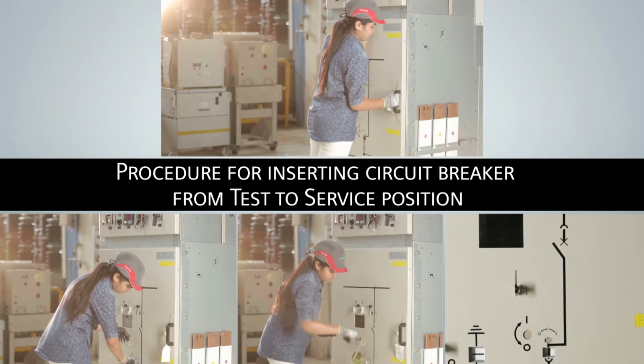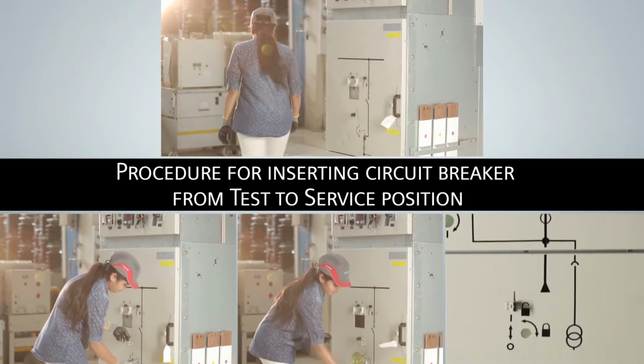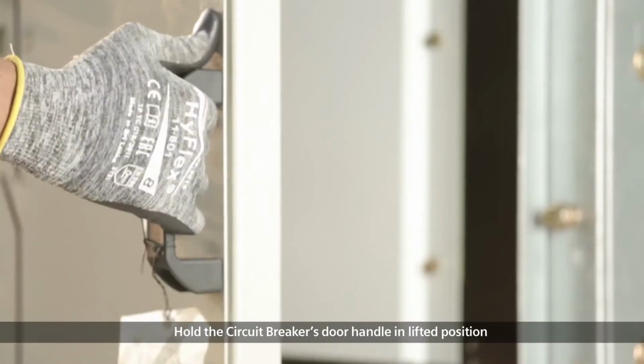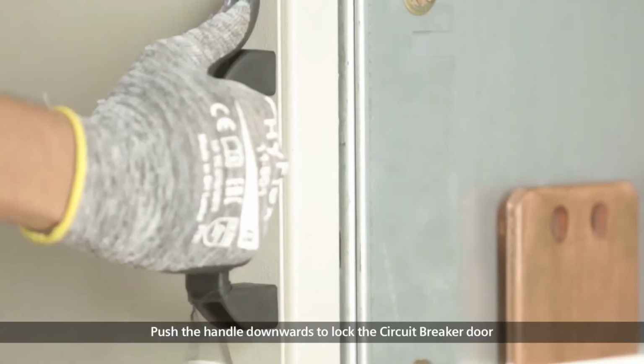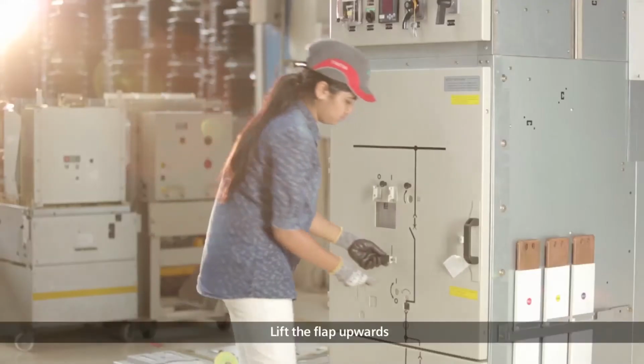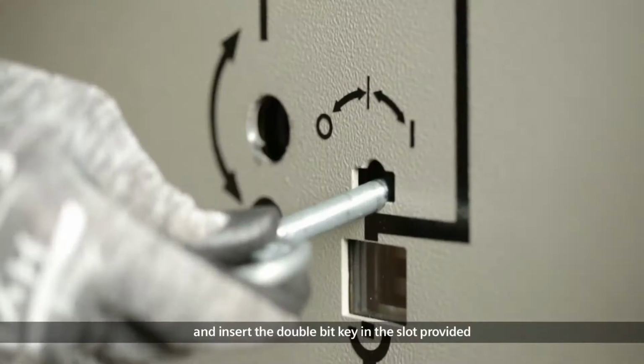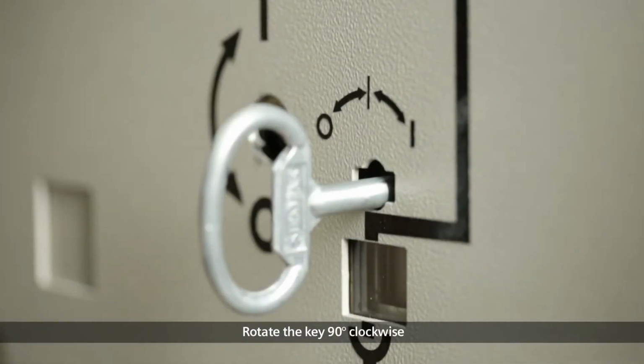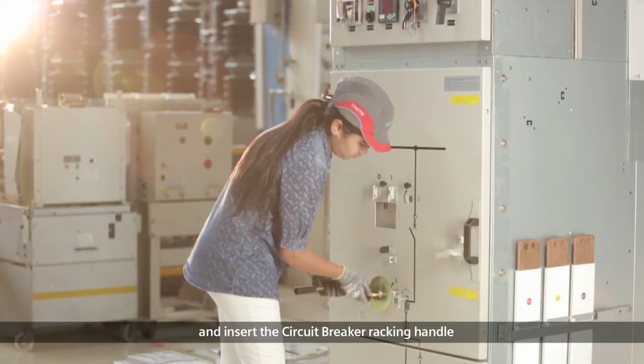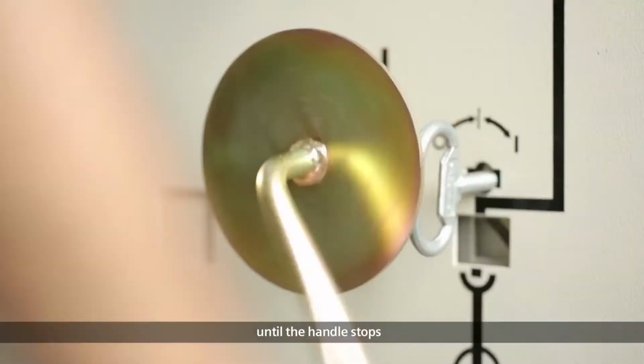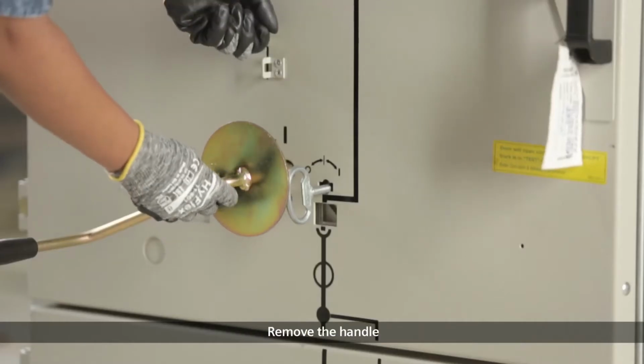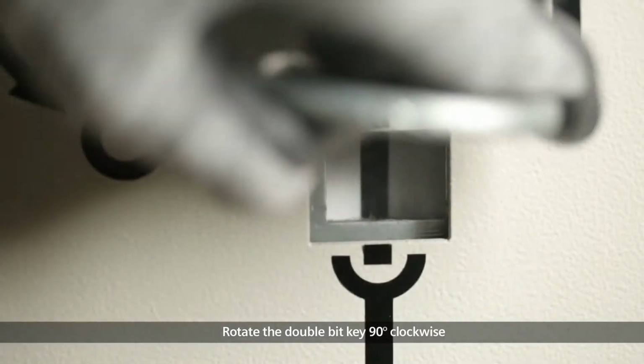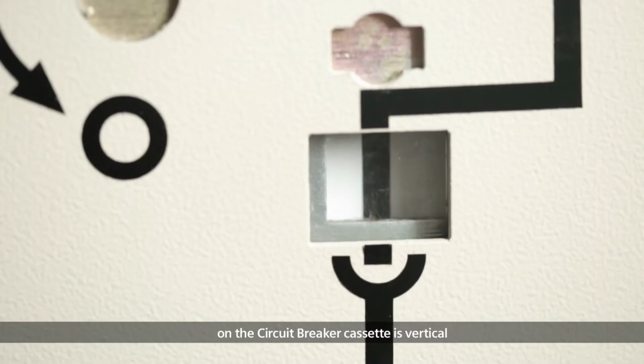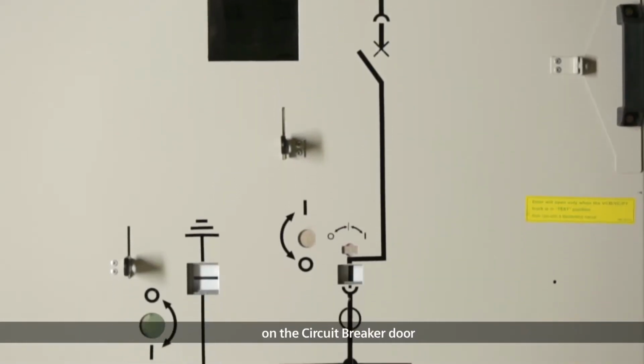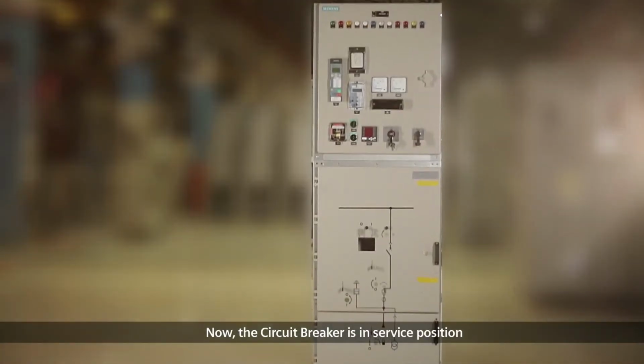Procedure for inserting circuit breaker from test to service position. Hold the circuit breaker's door handle in lifted position and close the door. Push the handle downwards to lock the circuit breaker door. Lift the flap upwards and insert the double bit key in the slot provided. Rotate the key 90 degrees clockwise and insert the circuit breaker racking handle. Rotate the handle clockwise until the handle stops after approximately 18 rotations. Remove the handle. Rotate the double bit key 90 degrees clockwise to remove the key. Check if the mechanical indication on the circuit breaker cassette is vertical and aligned with the virtual mimic on the circuit breaker door. Now, the circuit breaker is in service position.